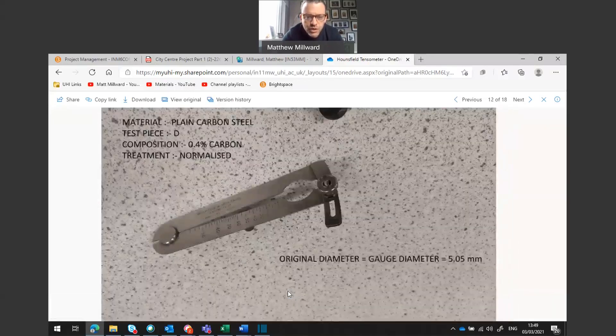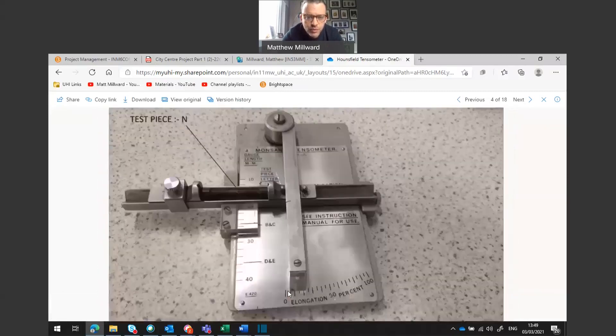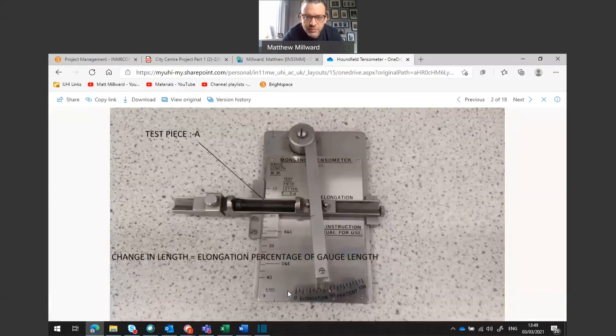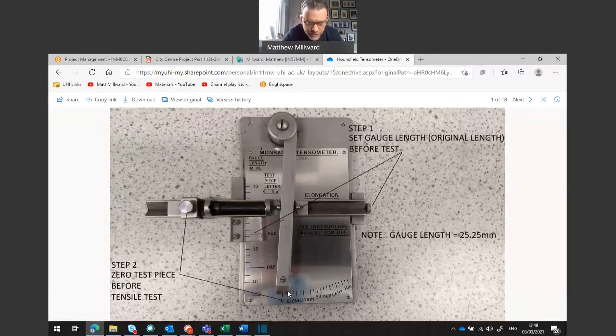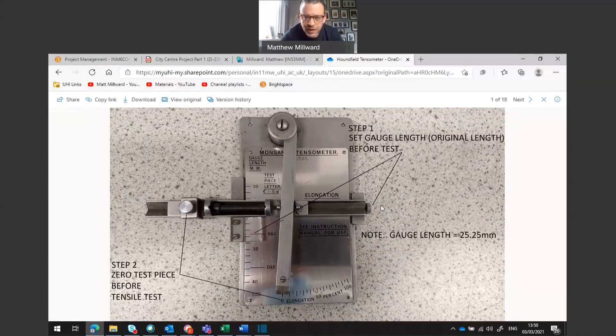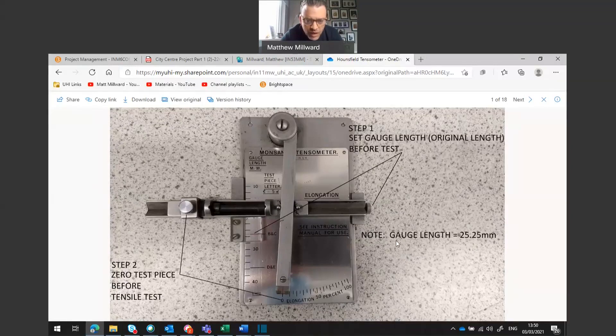I'm going to show you some pictures of what steel samples look like and some of the measurements that we will take before and after the experiment. Here we have a standard piece of steel that will work within the Hounsfield tensometer machine. We've got another piece of measuring equipment to measure the elongation of the sample. Before the sample goes into the machine it's set to zero. You can see the original gauge length is 25.25 millimeters, and this is all done before the tensile test is carried out.